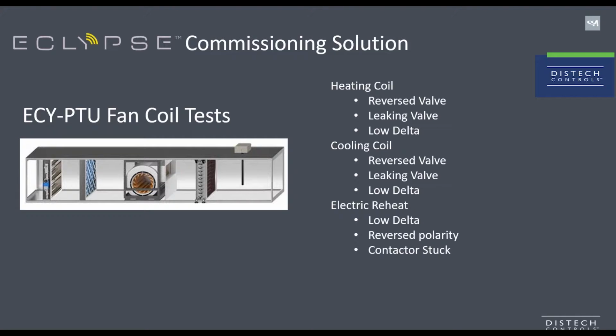When doing the electric heater test, the system will inform you if you have a low delta, a reverse polarity, or a stuck contactor. While doing the above test, the system will also energize the fan at low and high speed, detect the temperature delta, and inform you of any fan failure.